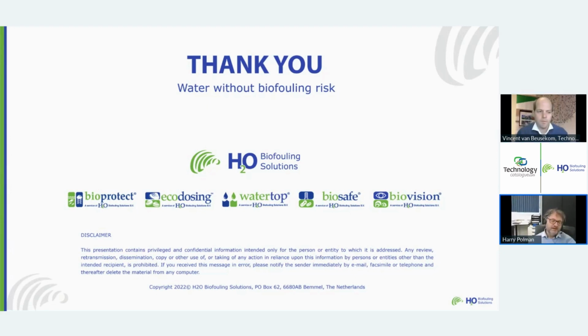Yes, chlorine is mentioned because it is still the most used biocide in the world, especially in seawater systems. However, the technology is based on the reactional behavior of the species to a biocide or fouling treatment procedure. We also have case studies where we used different products, for example peracetic acid, chlorine dioxide. We also used brine in freshwater systems. So we always look at what the best option is for a specific location, taking into account different products.